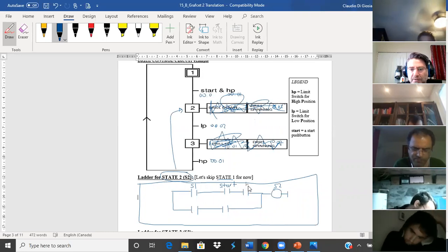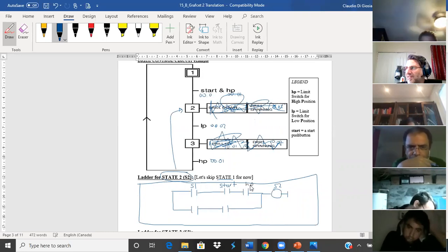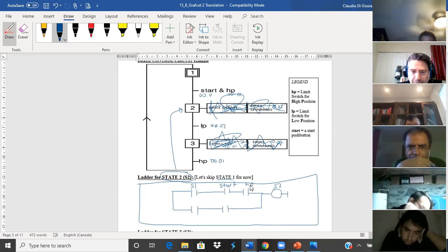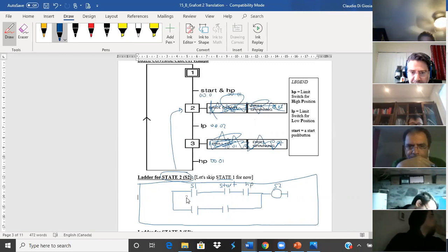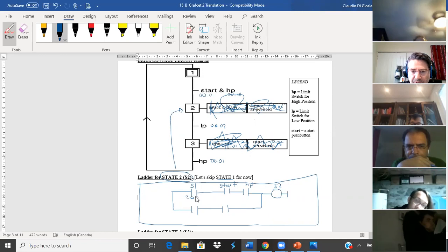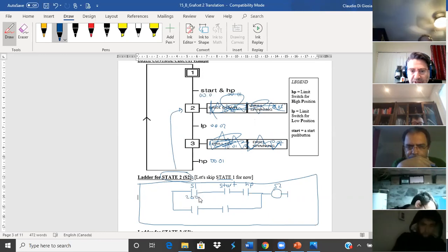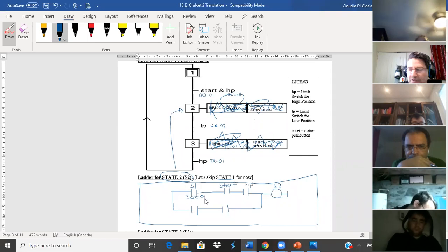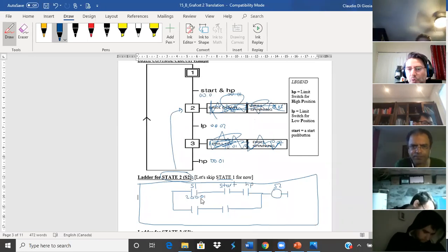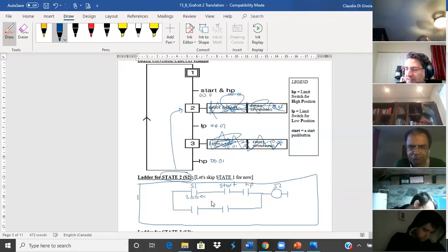The other condition is the initial position: the high position, meaning the drill press is up high — so 'high position.' What you should not forget to put in are the internal bits. We're using work bit 200. Since this is state one, I'm going to use 200.01 — this will be less confusing going forward.